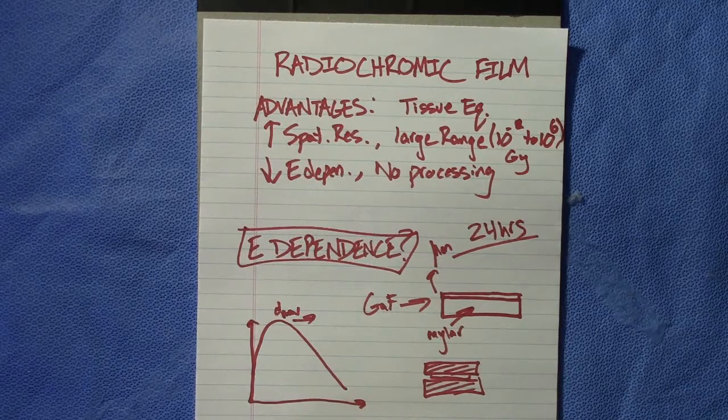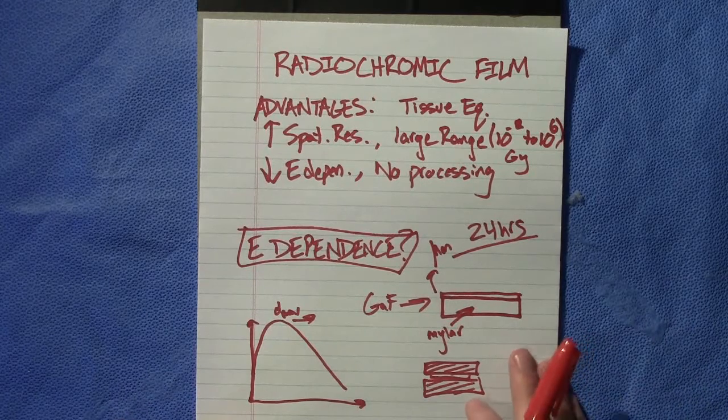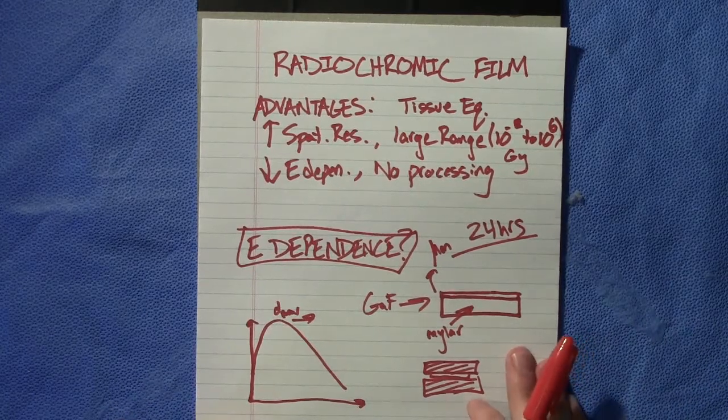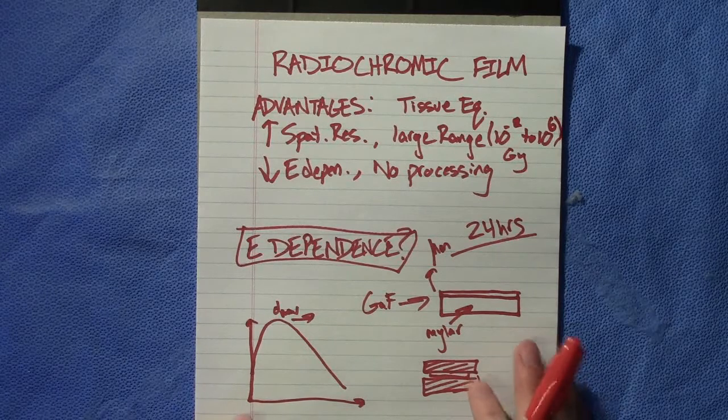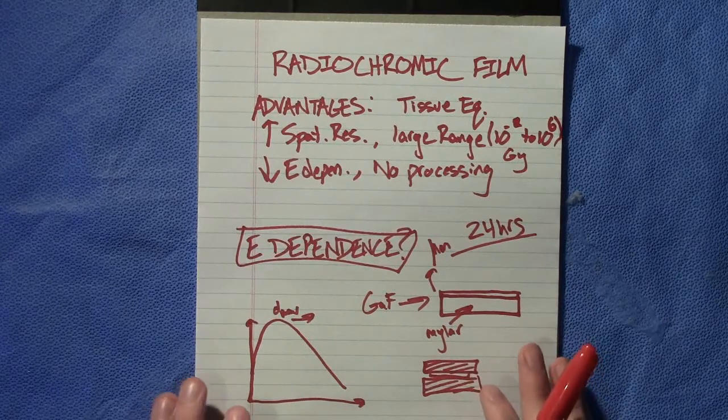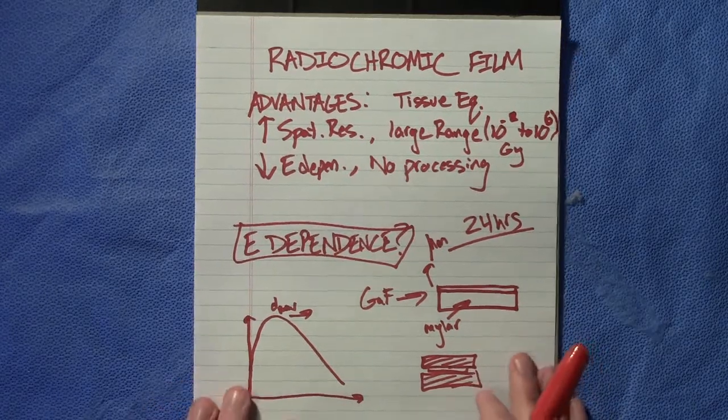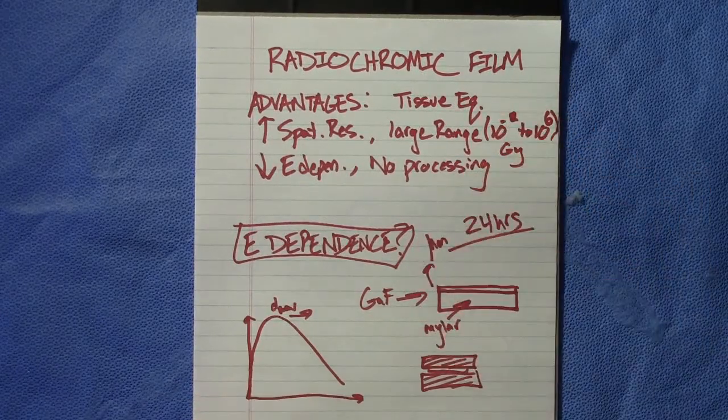Both from my personal experience and from everything that we know with radiochromic film, there is very little energy dependence for these, so you in fact can use the same film. You would think, since someone would ask that, maybe like a trick question, of course you can't use it. You've got to use different films for it, but not with radiochromic film. That's one of the big advantages, and that may be a question they throw out that may be a bit tricky, but really ensures that you know what you're doing with radiochromic film and you have used it in the past.